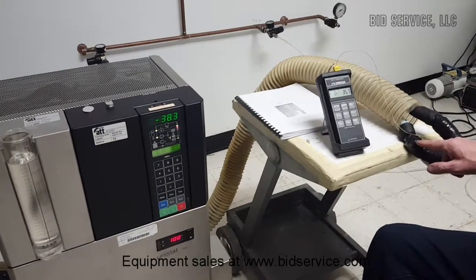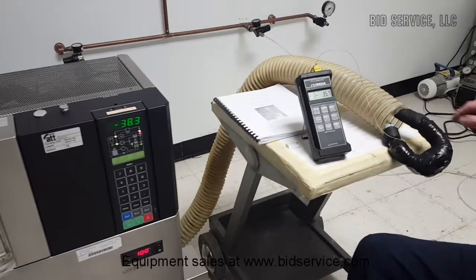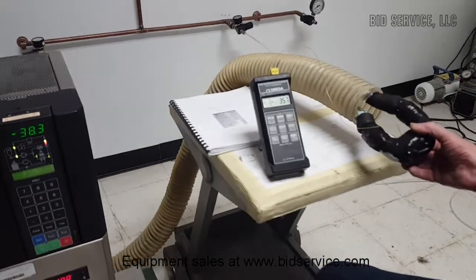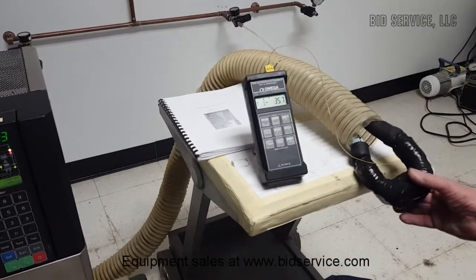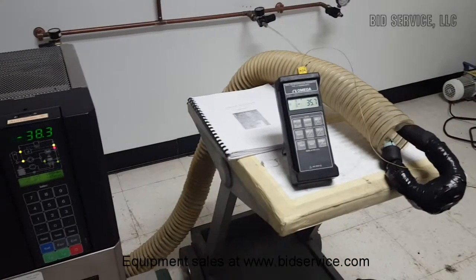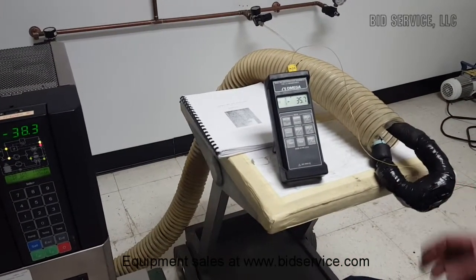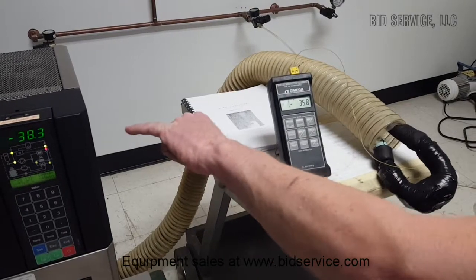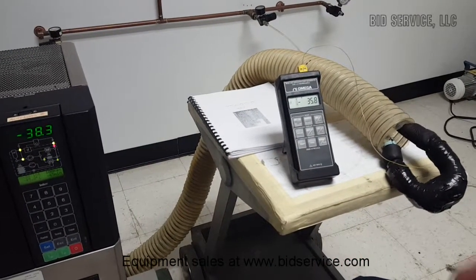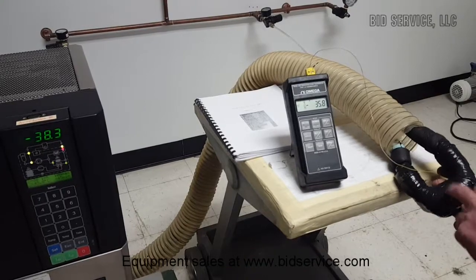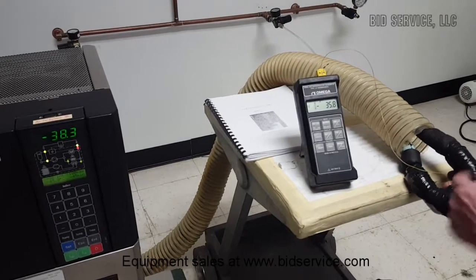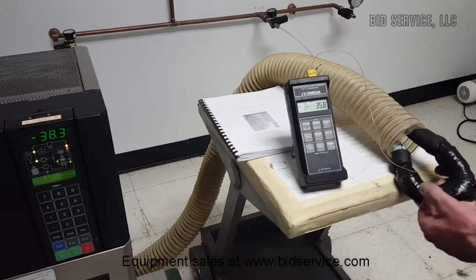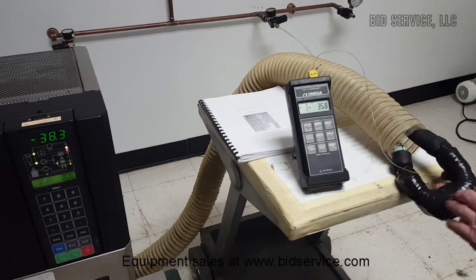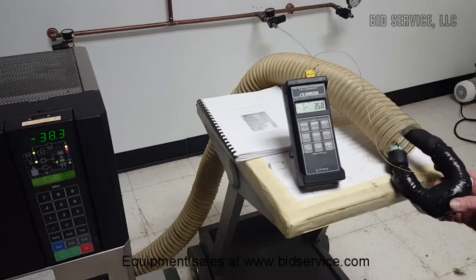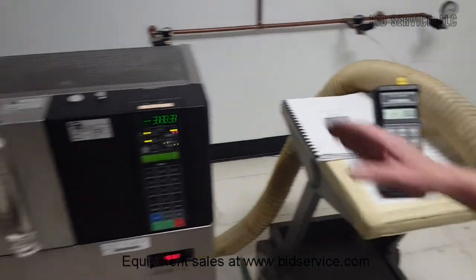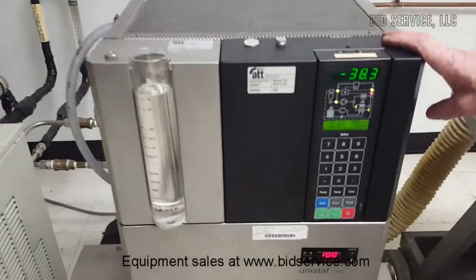I have a heavy wall stainless steel adapter in here. As you can see, even well insulated, it is frosting through a little bit. The 3 degrees differential in temperatures would be that particular temperature probe is directly in the fluid. Here I've just attached a thermocouple to the outside of the stainless steel. But even through the thick wall of that stainless steel, you can see that even the end of this little makeshift thing is down to almost minus 36 degrees. So again, the first part of our demonstration is to show you its cooling capacity.